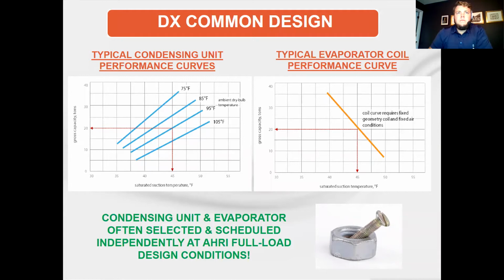So you can advance the screen. Also, the two pieces might not be made by the same manufacturer. We might have a condensing unit from brand A and a coil from brand B. We see this a lot. Just to follow up, as we noted here too, the most common way we see it designed, the status quo, is to schedule your condensing unit separately and your evaporator, your air handler and your coil, separately, independently at AHRI full load design conditions. Go ahead, Mike.